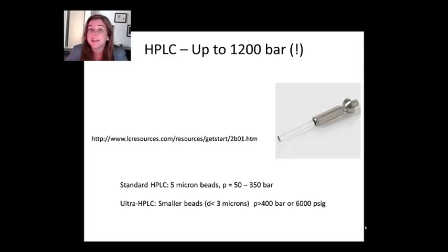So here are just some conditions that you might see on HPLC. A standard HPLC might be 50 to 350 bars, which is fire hose or a little bit more. But if you go to ultra HPLC, which is going to give you much higher resolution and faster separations, really what you're paying for is a system that can really deliver those much, much higher pressures in a way that's very smooth. So they spend a lot on the dampers and the pump design so that you can achieve those pressures without any fluctuations in flow rate.